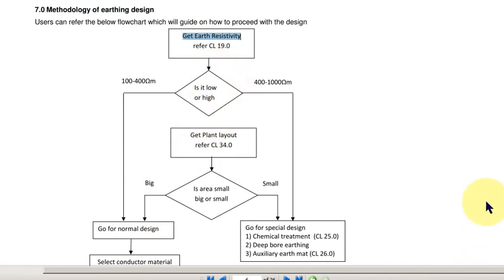you have to check whether the resistivity is low or high. If the resistivity is from 100 to 400 ohms or much lower, you can go for normal design. If the resistivity is very high, then you cannot go for normal design.